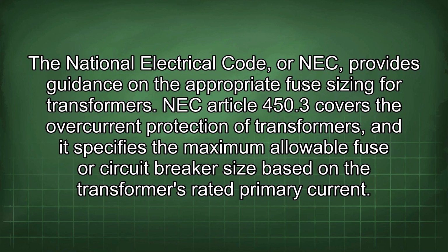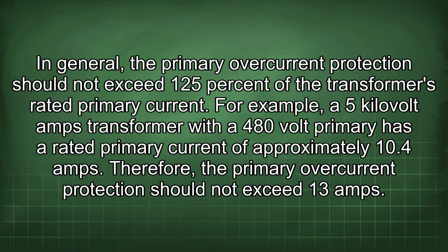The National Electrical Code, or NEC, provides guidance on the appropriate fuse sizing for transformers. NEC Article 450.3 covers the overcurrent protection of transformers, and it specifies the maximum allowable fuse or circuit breaker size based on the transformer's rated primary current. In general, the primary overcurrent protection should not exceed 125% of the transformer's rated primary current. For example, a 5 kVA transformer with a 480 volt primary has a rated primary current of approximately 10.4 amps. Therefore, the primary overcurrent protection should not exceed 13 amps.